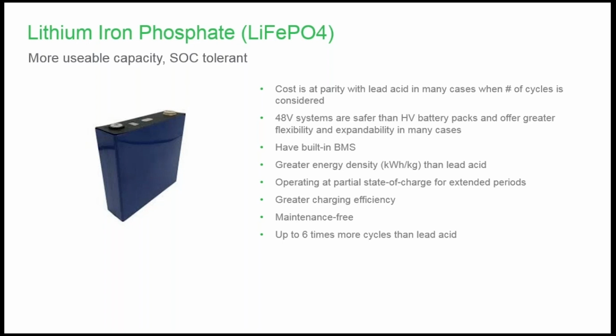48 volt systems are safer than high voltage lithium packs, and offer greater flexibility, expandability, and stackability. I've seen lithium banks quite large with 48 volt systems. They're all going to have a built-in BMS, whether they have communications with external devices or not. They have a greater energy density, so they pack more power with lighter weight. They are state of charge tolerant, so you can leave them at a partial state of charge for extended periods and that won't be detrimental to the state of health of the battery. They are more efficient battery chemistries than lead acid. They are maintenance free as well, and they offer up to 6 times more cycles than a lead acid battery.